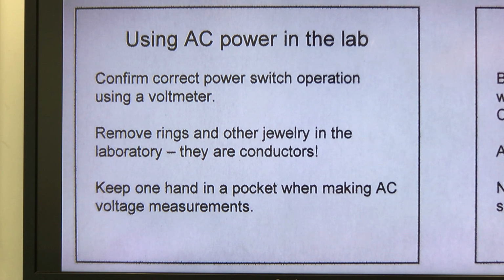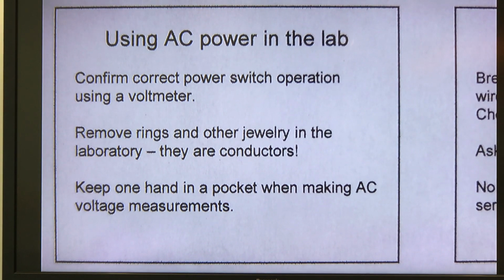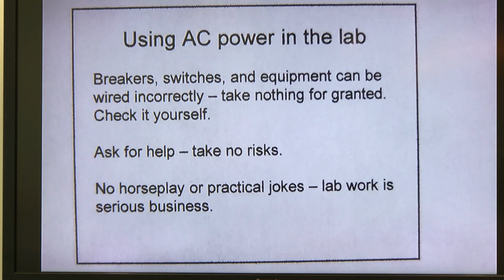And what I do when I have to measure stuff inside the power connection, I use an alligator clip for the ground or for the low side of the measurement. I hold the probe for the hot lead in one hand and I put my other hand in my pocket. If you don't touch it to anything metallic, you're going to be fine. So I encourage you to follow those rules. Breakers, switches, other equipment in the power system, it is possible, it happens, that those can be wired incorrectly. Take nothing for granted. Check it for yourself.